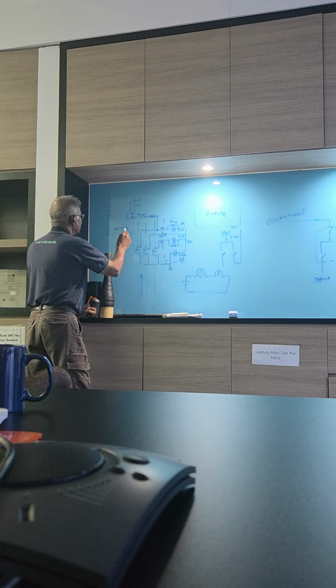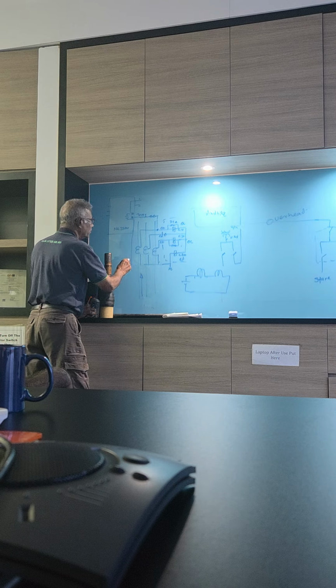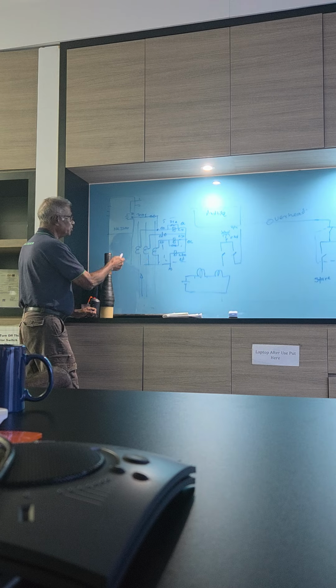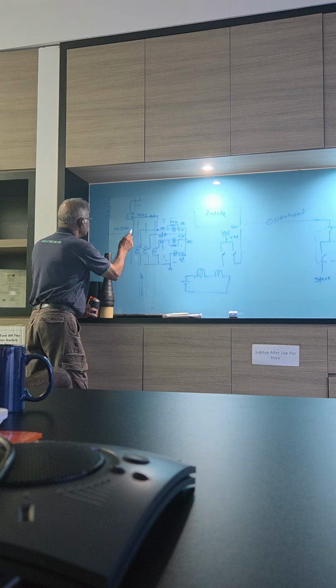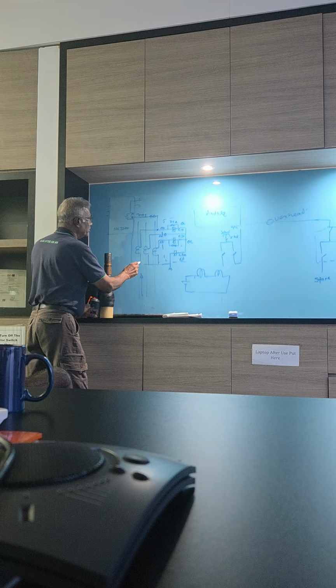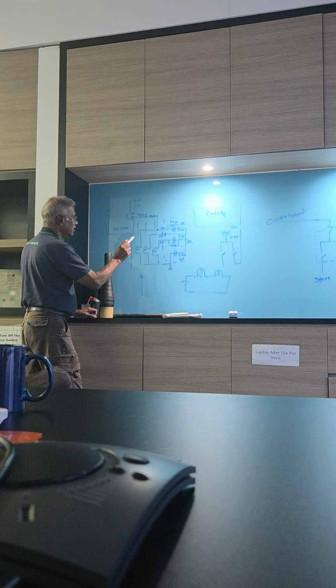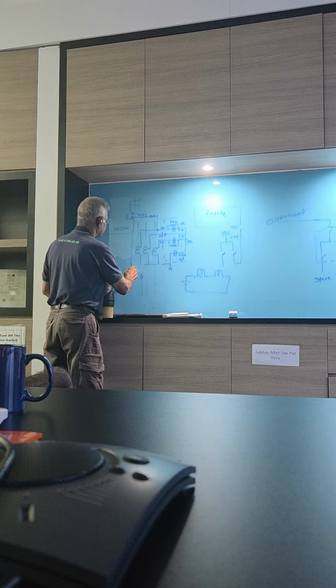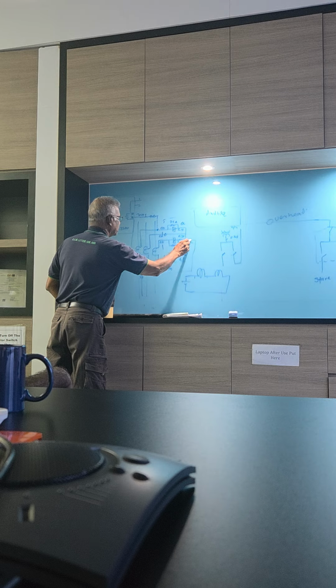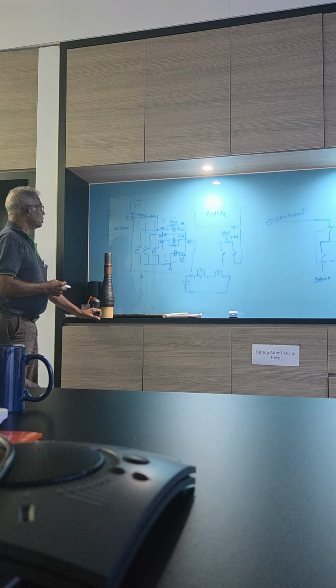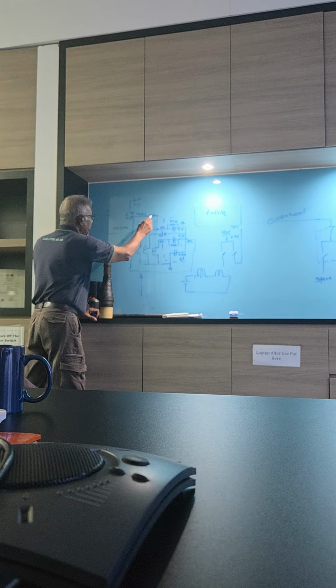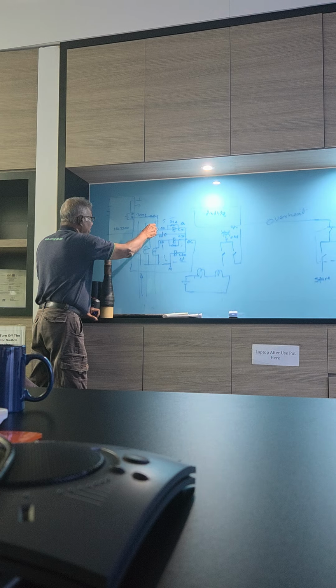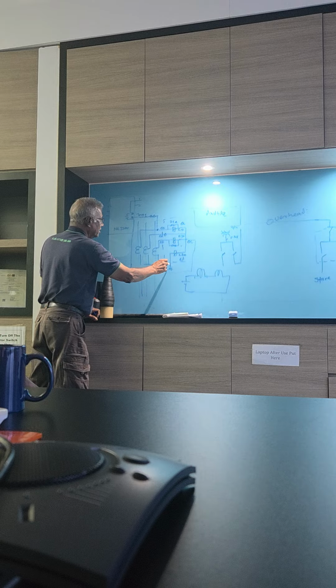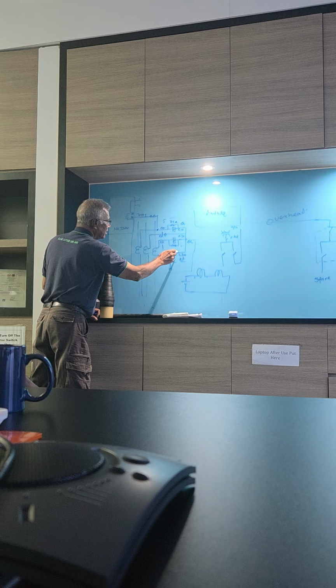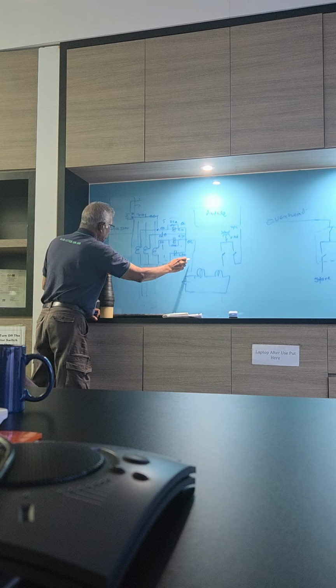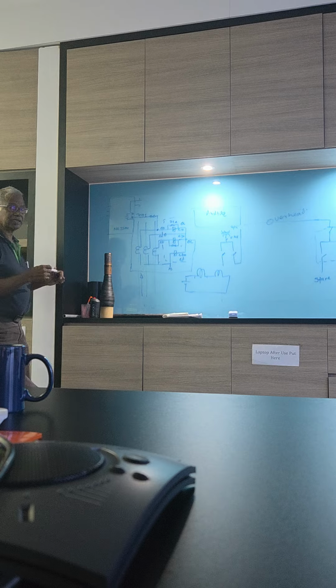And then this one was supposed to go to a relay. Which relay? So this is supposed to go to a relay. So this went to C30. So it went to this terminal. So that means external power has gone into this CT. It went into this CT coil, came back here, and then went to this solenoid, this shunt trip, and back this way. That means there was a complete circuit.